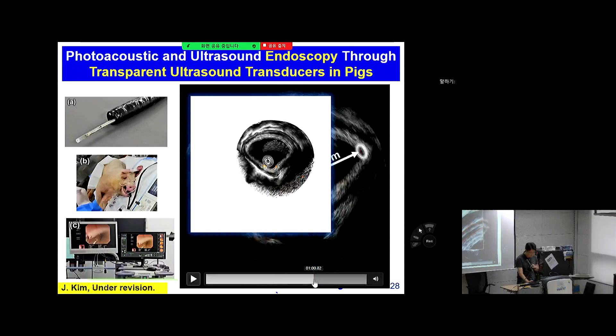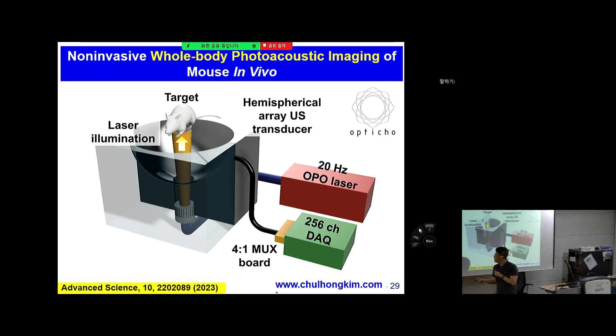Right, maybe I can skip a little bit. These are all 3D, we can render in 3D. So now I can move to the whole body imaging scanner. Previously the system was cheap because we used only a single element transducer. If you pay more money, like if you use more elements of the transducer, you can provide a better image quality. Also we can use high data acquisition systems. So we use a 1024 channel ultrasound element, which is a ball shape, and then we use 256 data acquisition systems. So these are the whole body imaging scanner.